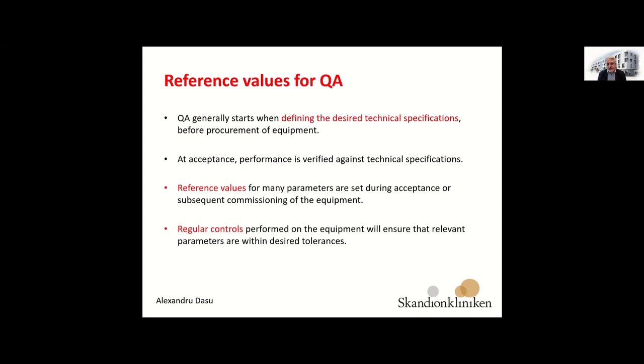So I said that you have to check and you have to compare the results of your measurement to a value, a desired or a reference value. And you have to think that quality assurance as a process generally starts when you define the desired technical specification for the equipment that you want to purchase. So it's very early in the process that you have to think about what you'd like the equipment, or the method that you are devising, to perform in practice. And that in a way sets the stage for your process. It's always very difficult to go up afterwards. So if you, let's say, bought a system that doesn't have a very brilliant technical specification, it's very difficult to make it, a posteriori, perform better than it actually does.